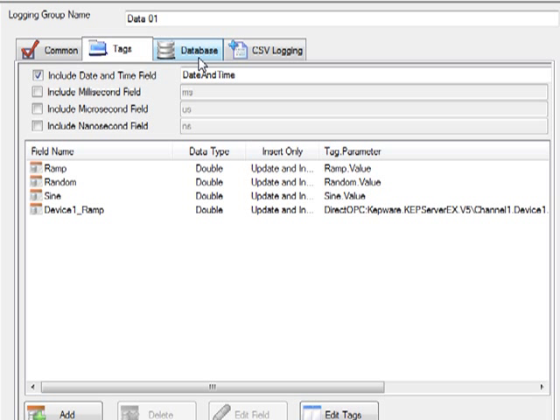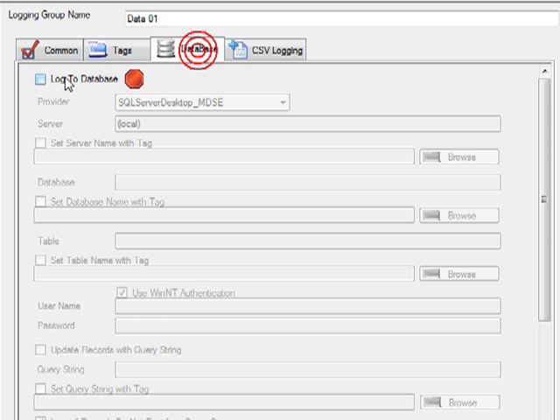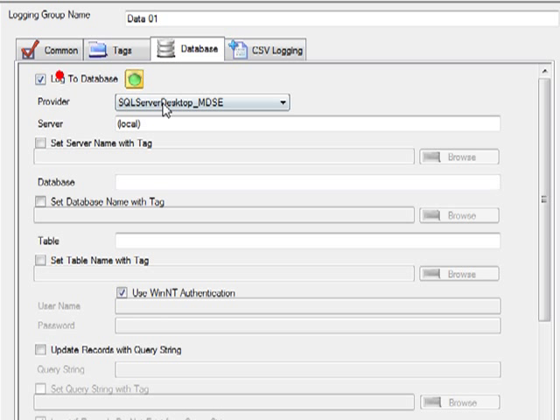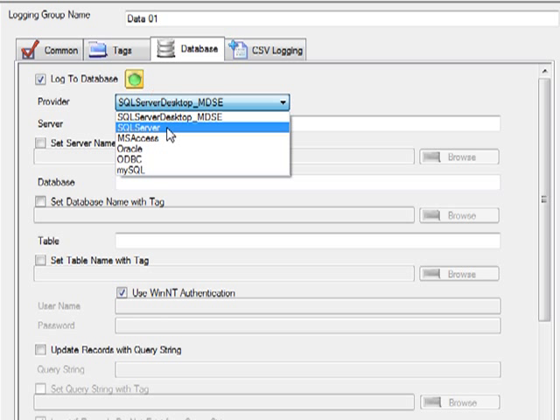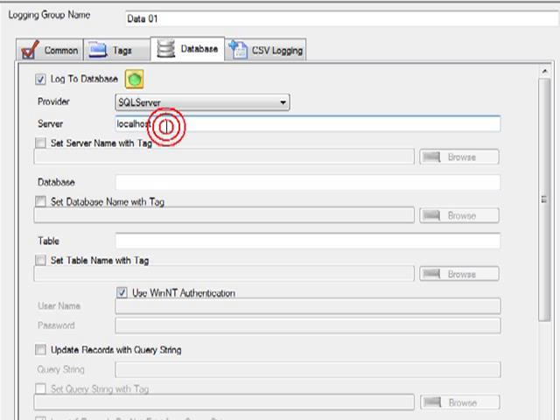And now we're going to specify where it is that we're going to log these values. Under the database tab is where we can specify what database provider we're going to use. SQL Server is very popular, but you can also use Oracle, MySQL, Microsoft Access, and ODBC. When you use the Oracle and ODBC types, you will have to specify the database first. With Oracle, it will automatically create the tables. With ODBC, you'll have to create the tables yourself. With SQL Server, it'll do it all for you.